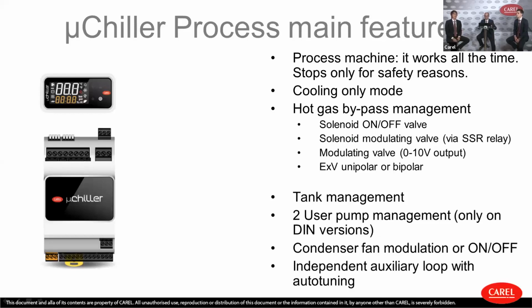The hot gas bypass management is very important. It's a dissipative method, but it's proven to be really fast — by far, traditionally, it's what everyone was using. So even if it seems against current trends, we've made it really versatile, so you can set it up with an SSR relay. By the way, it's embedded, so you don't need to add an extra module — we give you the SSR directly in this controller.